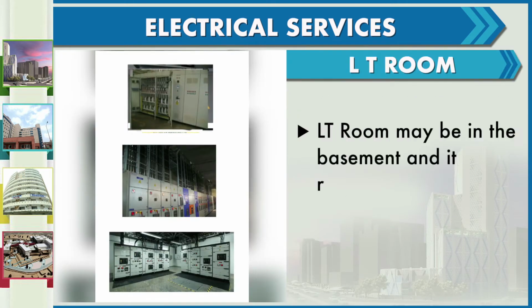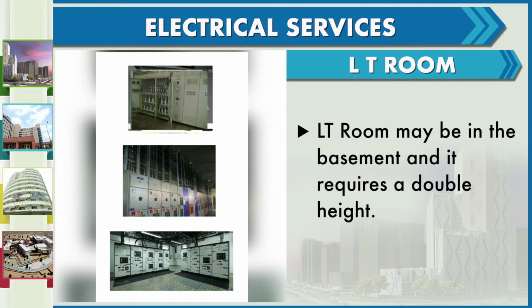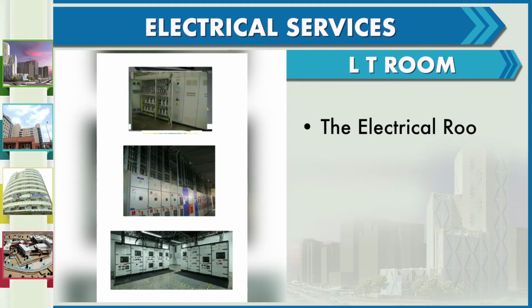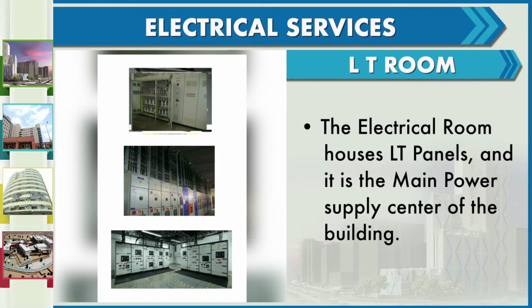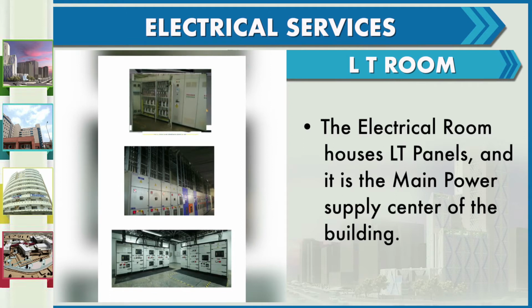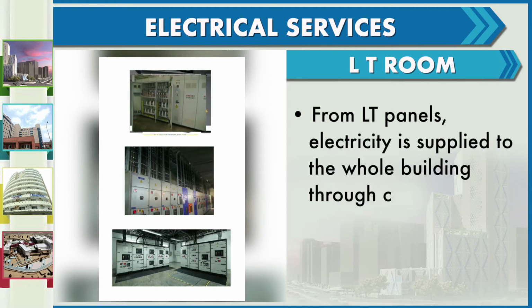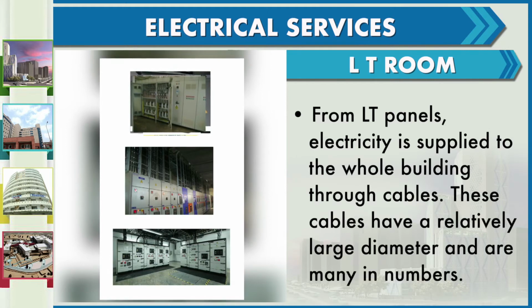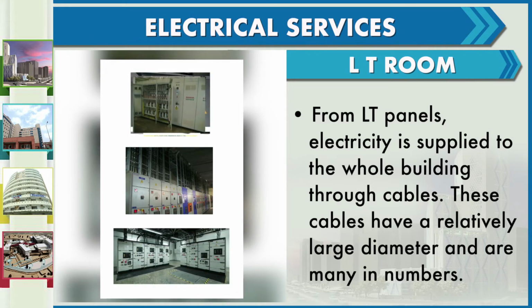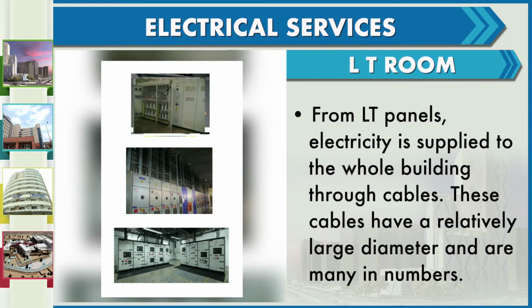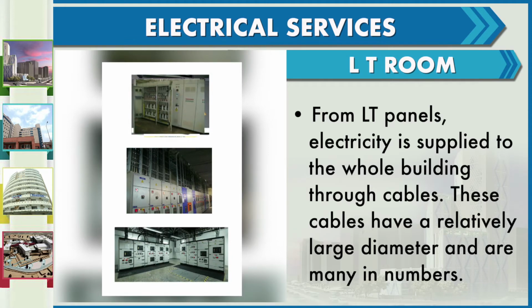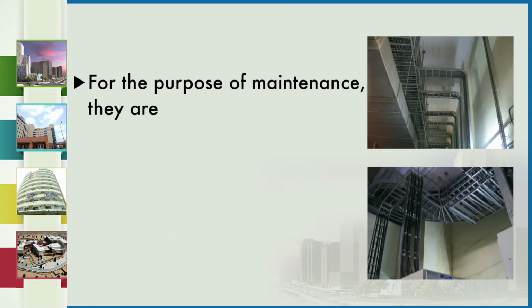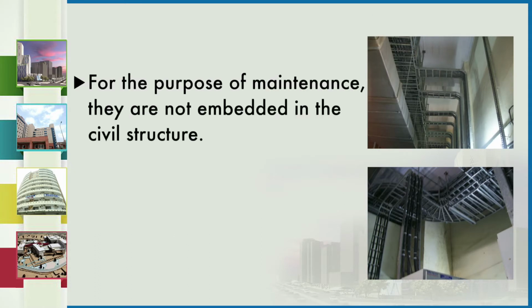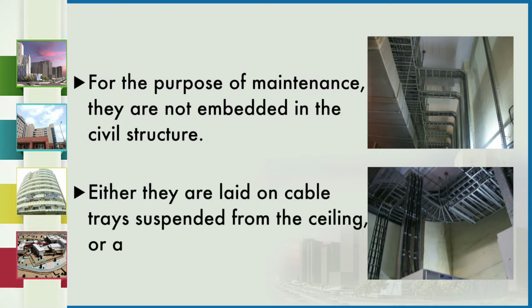Now the LT room may be in the basement and requires a double height. The electrical room houses LT panels and it is the main power supply center of the building. From LT panels, electricity is supplied to the whole building through cables. These cables have a relatively large diameter and are many in numbers. So for the purpose of maintenance, they are not embedded in the civil works like we do in normal buildings. Either they are laid on cable trays, suspended from the ceiling, or are clamped to the ceiling.